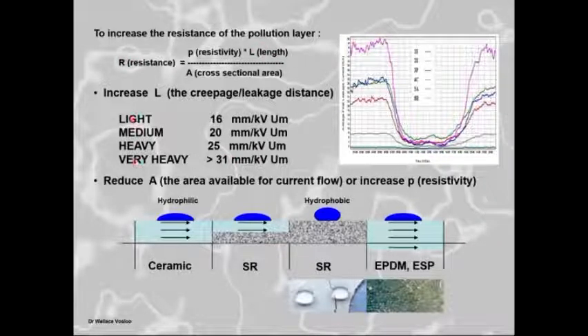That's why you choose different creepage distances. Now, when we start looking at the cross-sectional area, the area available for current flow, well, if this is a ceramic insulator and it's got a pollution layer of a certain thickness, which will now determine the area available for current flow, it's hydrophilic, it wets out totally. We use that as a reference, okay?